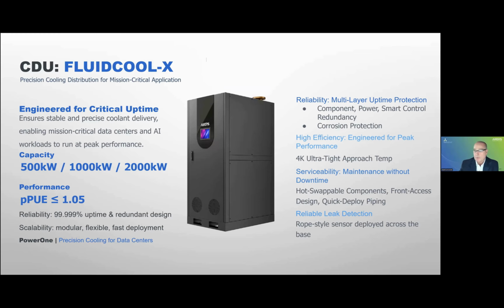Our fluid cool CDU. Again, this is engineered with space in mind. It's designed to fit right into a row of enclosures if necessary. It comes in 3 different capacities: the 500 kW, the 1 megawatt, and 2 megawatt. We did this specifically to match up to the chillers, but because we know everyone wants to go bigger, we're in the midst right now of designing a 3 megawatt CDU, and we are talking to clients about customized larger units up to 10 megawatts. The nice thing about this product is the hot swappable components, 99% front accessible for any type of service needs if there's an issue with the unit. There are a number of different leak detections, but also internal detections for inside the steel. And we're using stainless steel 316 to help mitigate any type of degradation to the fluid inside of the CDU.